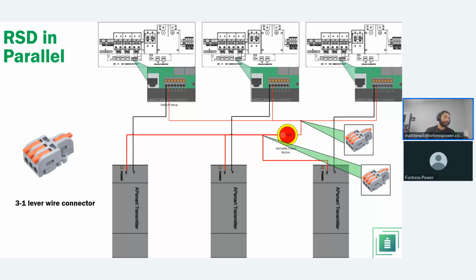Now, the second option would be to get a rapid shutdown button that has multiple connection points. I think there are 3-pole, 4-pole, 5-pole, or 6-pole buttons where you can do this. Now they're a little bit more expensive, and that's why I recommend using the 3-to-1 lever wire connector, right? So you have 3 connection points here on the positive of each AP Smart transmitter, and they will land on this lever connector. And then from there, one cable goes into your rapid shutdown button. And then from there, you would go one cable landing into the one side of the lever connector, and then from there, split 3 ways into the positive port of the contacts.